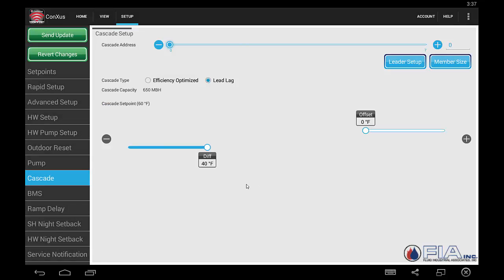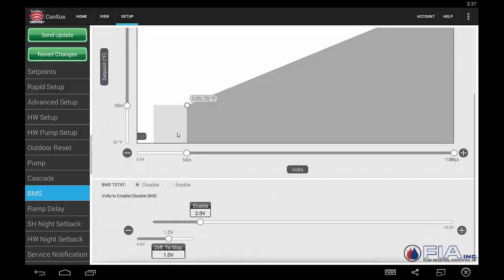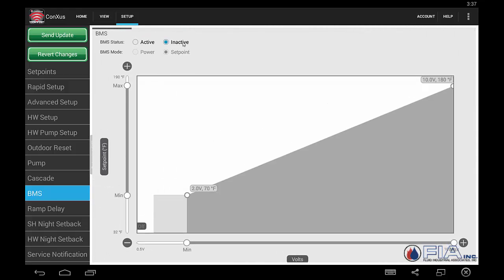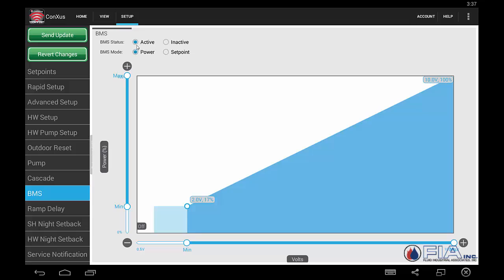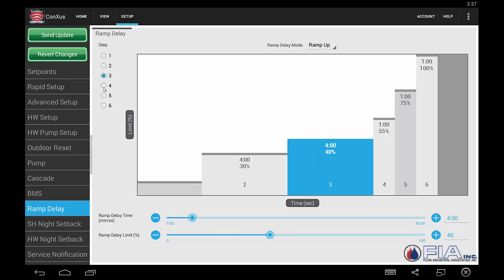We can turn our BMS on. In this case it's grayed out because it's inactive. By making it active, we can then determine if we are a set point or a power input on that zero-to-ten volt signal, and how we want the boiler to respond at the various points. Our ramp delay screen is going to set up our various stages of ramp delay, and at the bottom we'll pick the time and the limit for each stage.